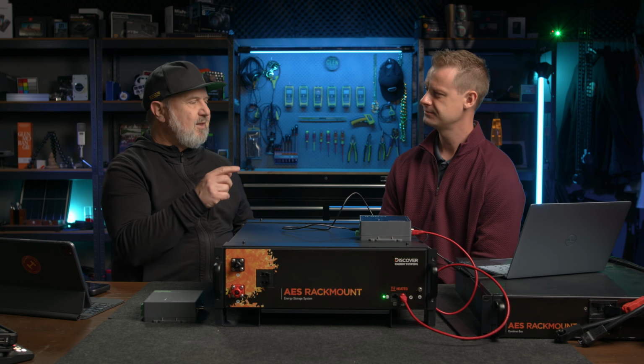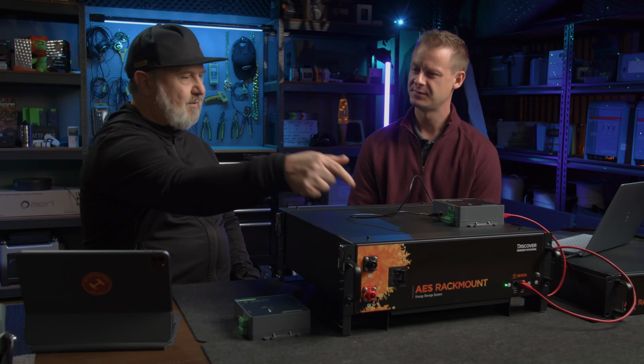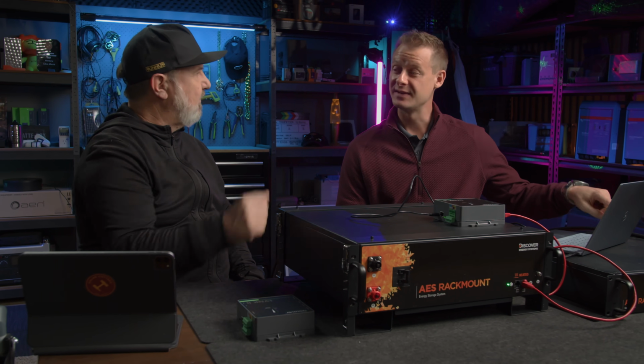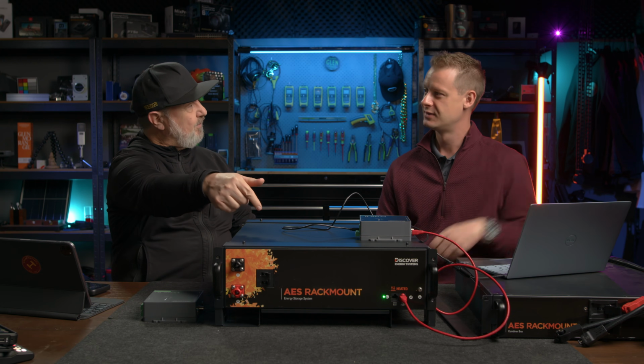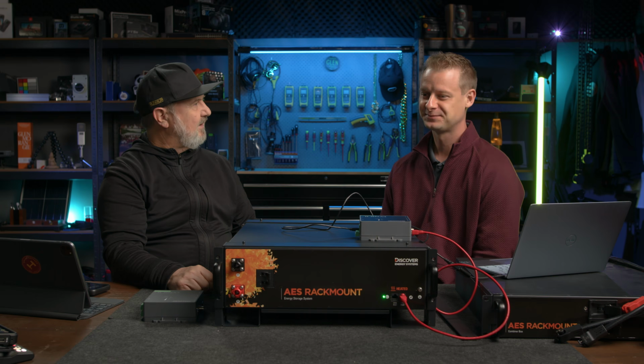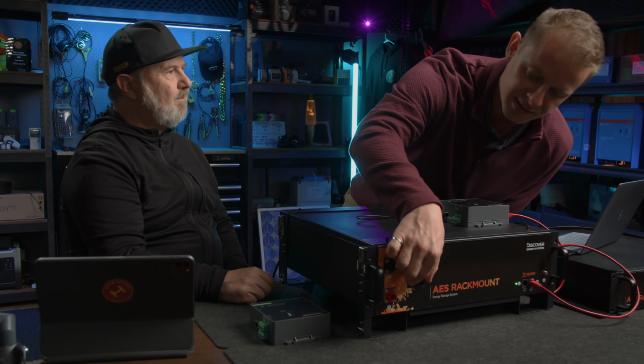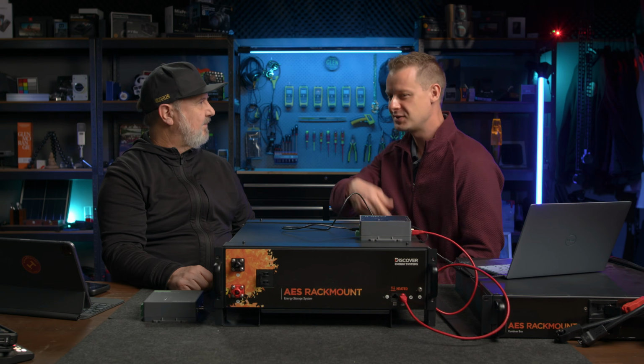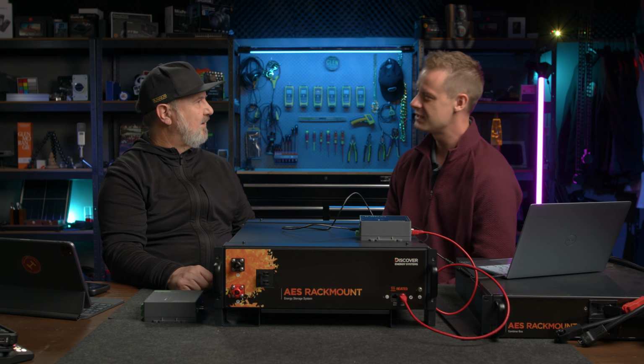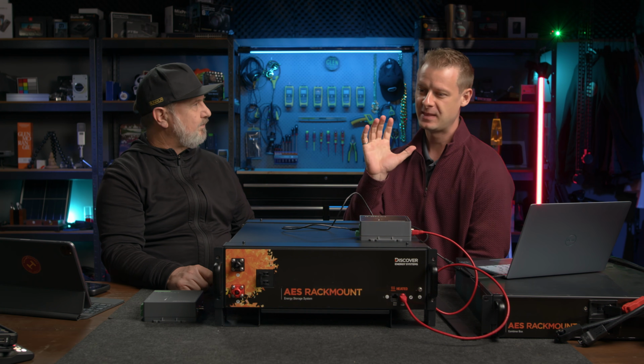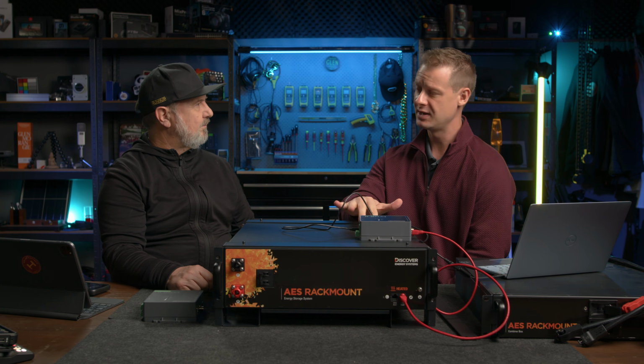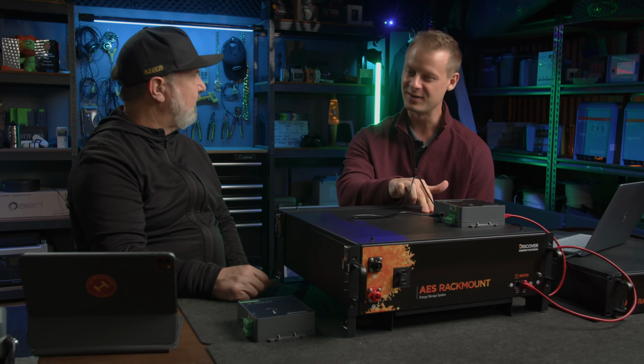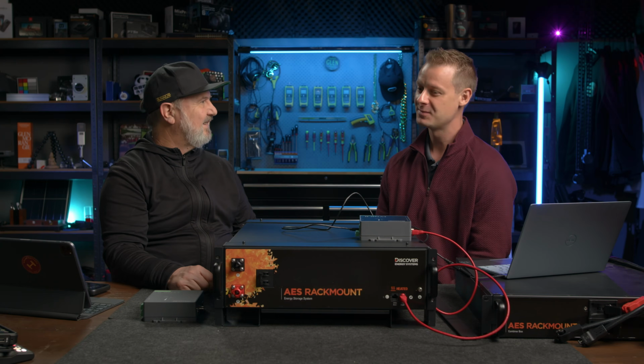So you said there's fusing on each battery - is that the circuit breaker on the front here? That's inside the combiner box. Oh right, so you've also got a breaker on the front. If you flip it over, the BMS will show it's in the off state, telling you the breaker's off. So we've got a breaker on the front that breaks the positive and negative pole - that was derived out of Australian requirements actually, you don't need it in North America at this time.